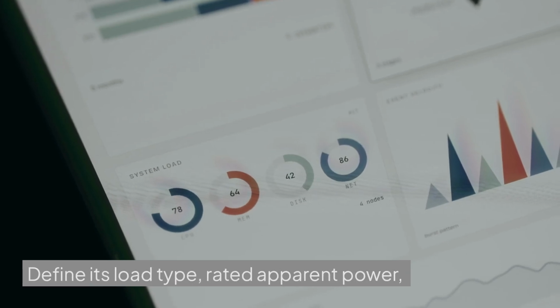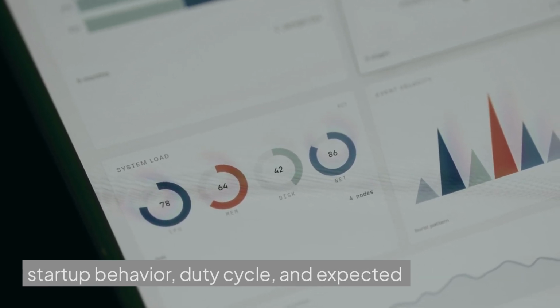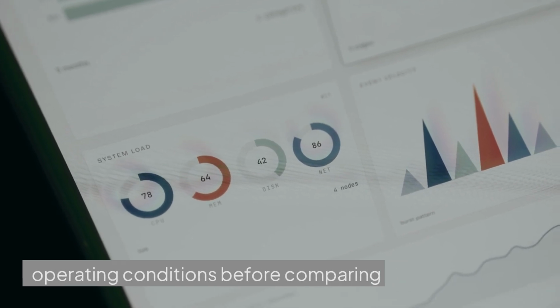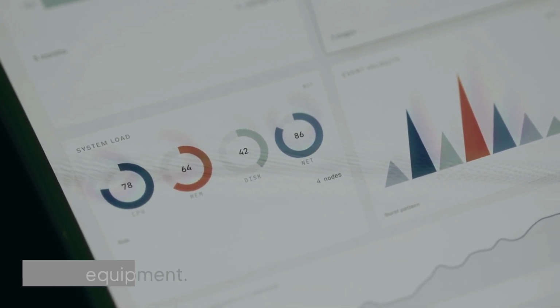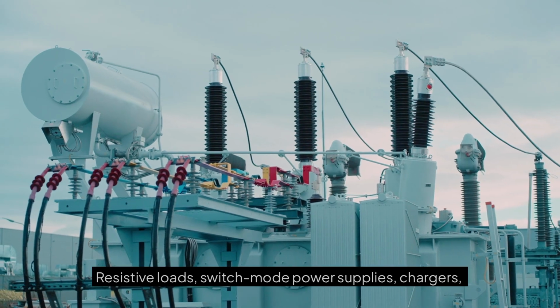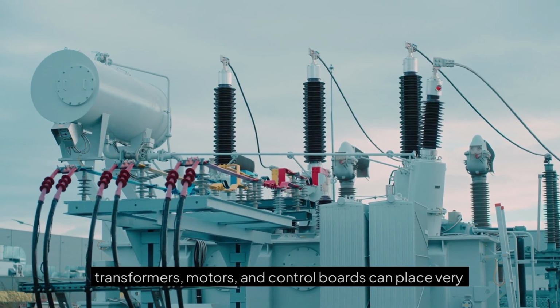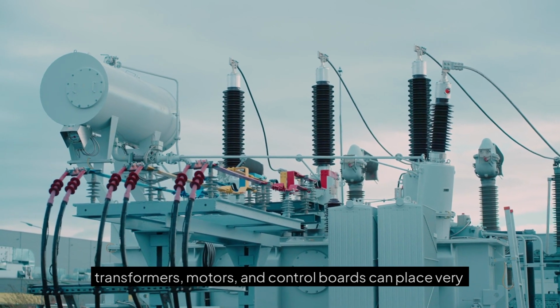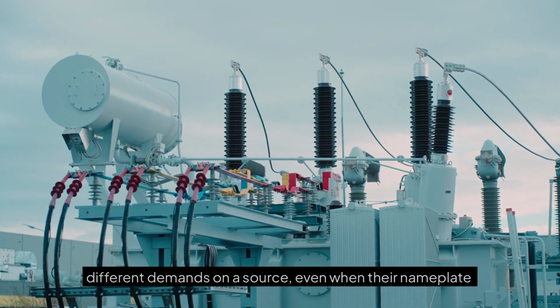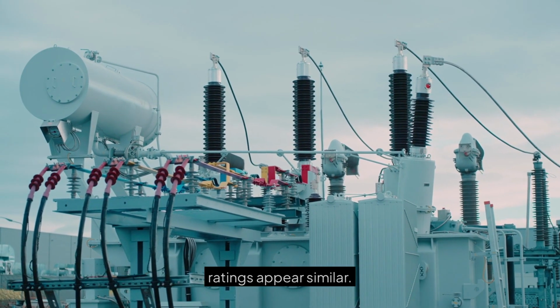Define its load type, rated apparent power, startup behavior, duty cycle, and expected operating conditions before comparing equipment. Resistive loads, switch mode power supplies, chargers, transformers, motors, and control boards can place very different demands on a source, even when their nameplate ratings appear similar. Treat VA capacity as a boundary, not a target.